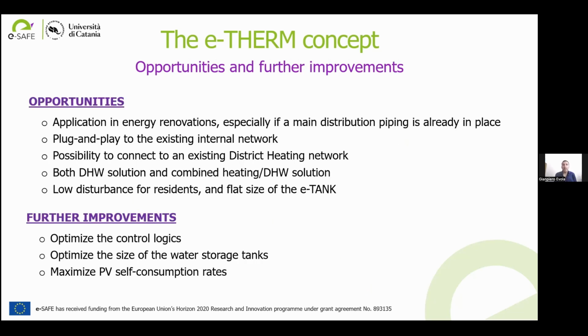So with our e-THERM concept, we have a lot of opportunity because we can apply it easily, or quite easily, in energy renovations, not only in new buildings, especially if the building already has a main distribution piping network. We can just replace the storage tanks and the generator. We can follow a plug-and-play approach also for the existing internal distribution network, I mean inside the apartments. We can also connect, if this is the case, to an existing district heating network, which is what we are doing in our virtual pilot buildings in Romania.